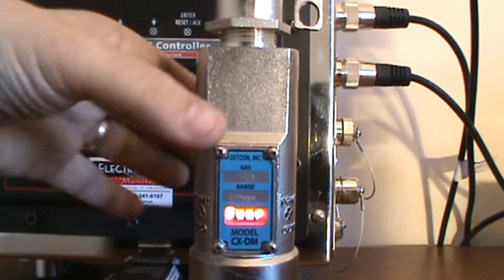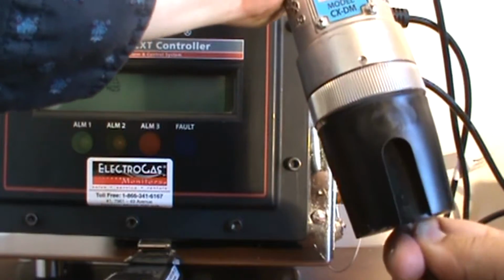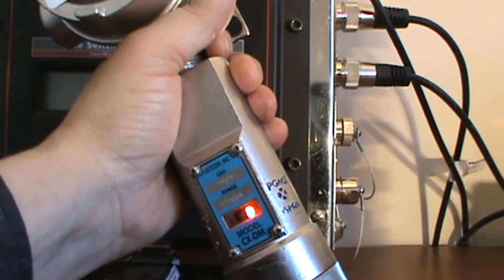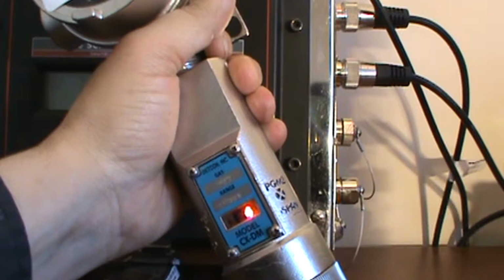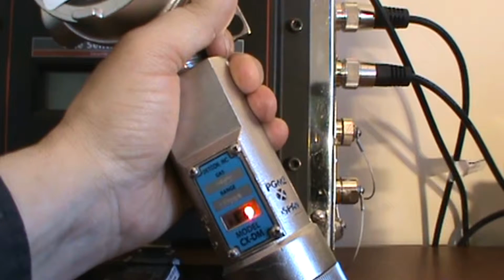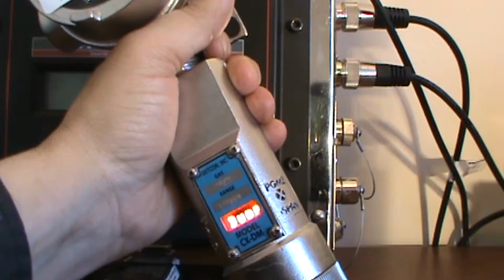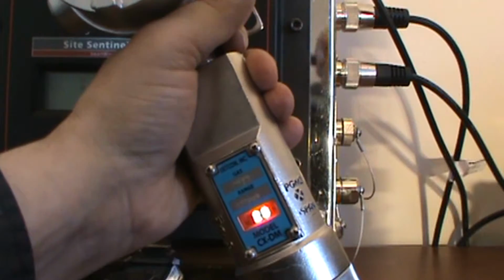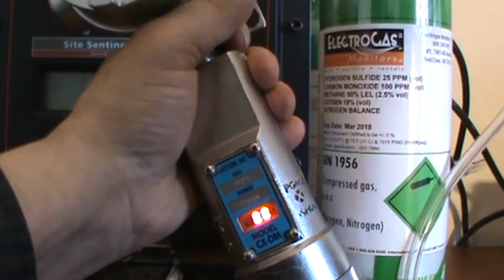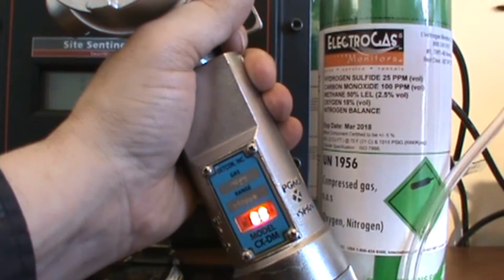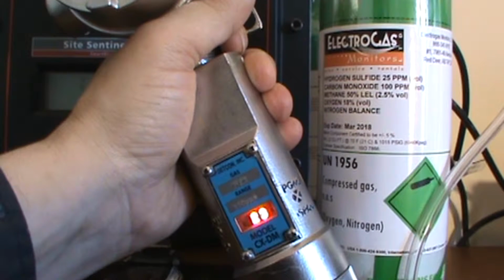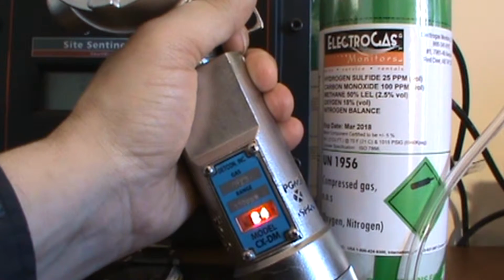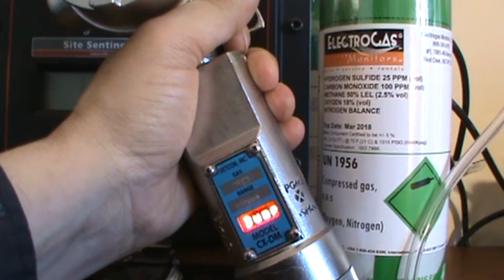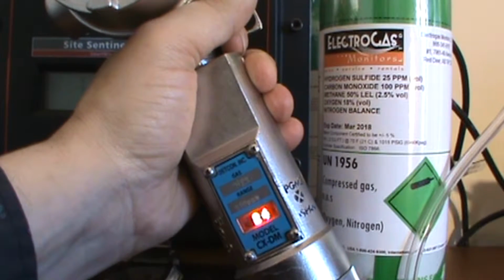And now we simply apply calibration gas and perform a bump test. But what will be different in this test is because we are actually in a bump test menu on our sensor, we are disabling the signal we're sending to any relays, therefore staying silent. And the goal in this bump test is to confirm that I can actually reach the same concentration on my display that I have in my gas. I'm using 25 parts per million H2S on my calibration gas, and I can see here that I've reached 24. That qualifies as a successful bump test.